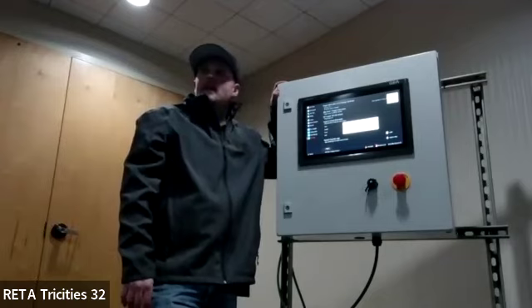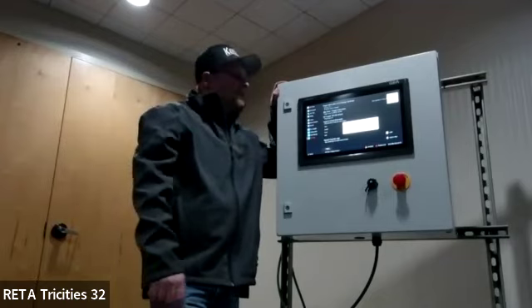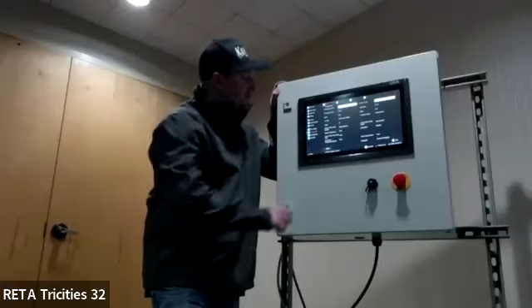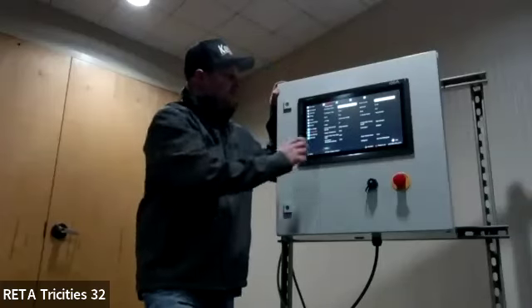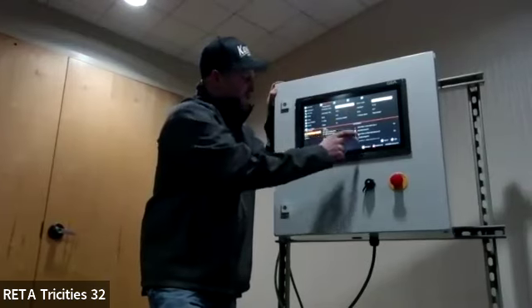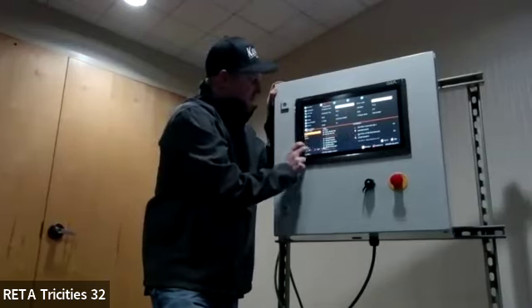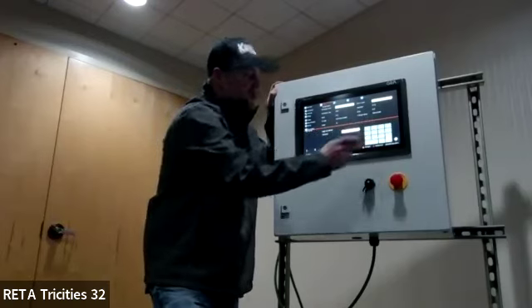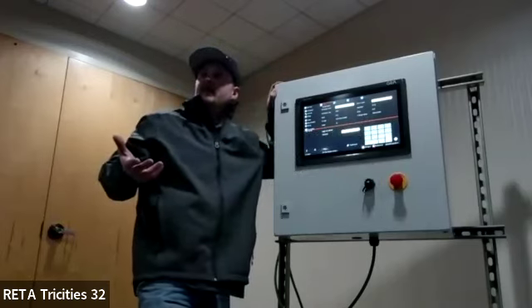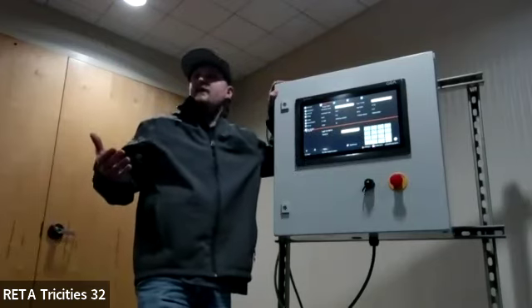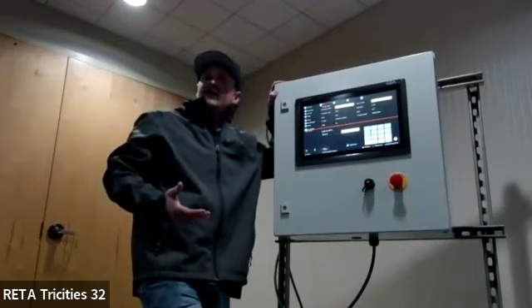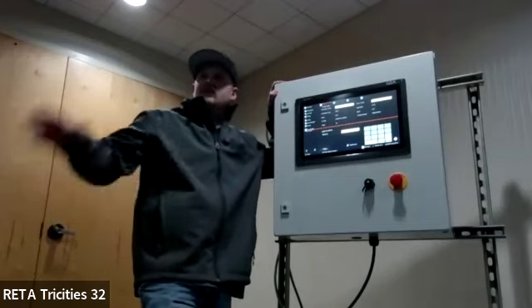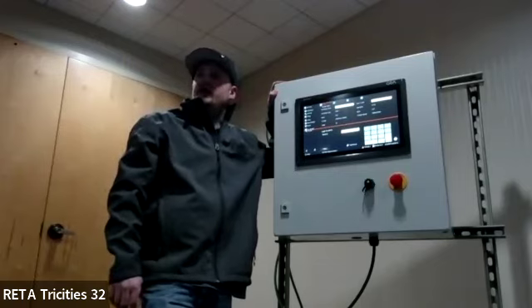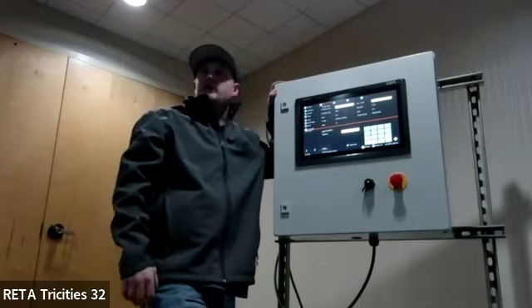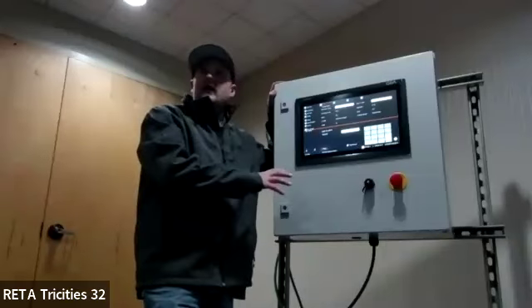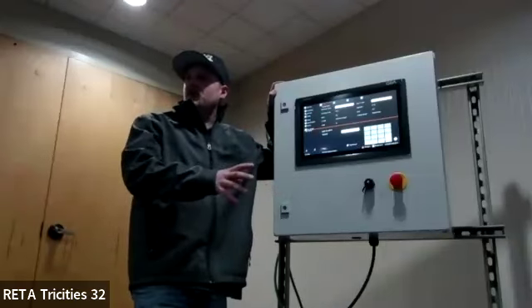What's the minimum anti-recycle time on those? Let's see if you can actually change that in the configuration if you're logged into admin. I believe you can. Is it accessible through service? How far are you trying to get, David? 20 minutes is what it's going to be defaulted at. But if you have a drive, you don't really need an anti-recycle, since it's on a drive and you can start and stop it. With a across-the-line starter, you're going to want to wait your 20 minutes. I believe if we log into admin, we can actually change that down.